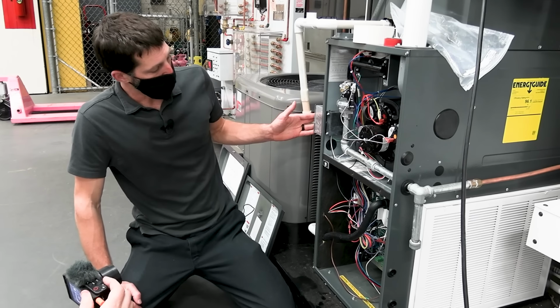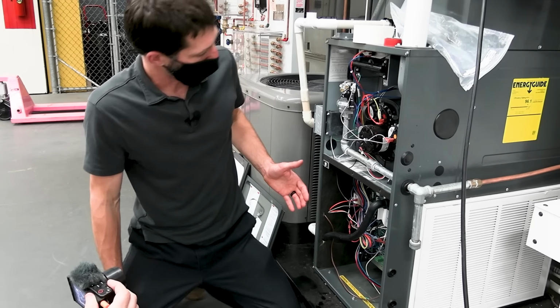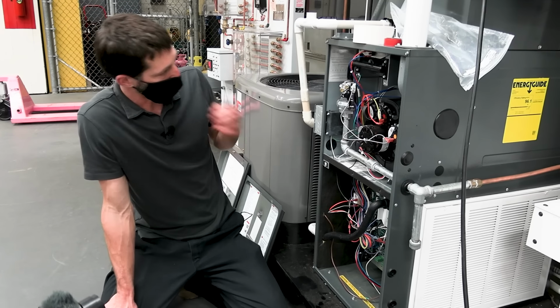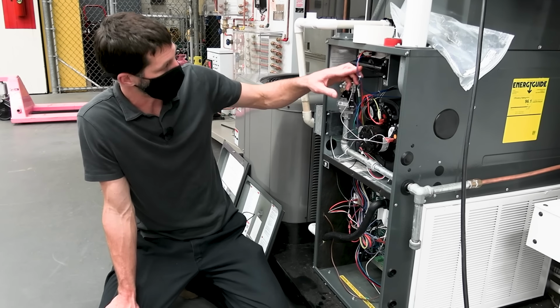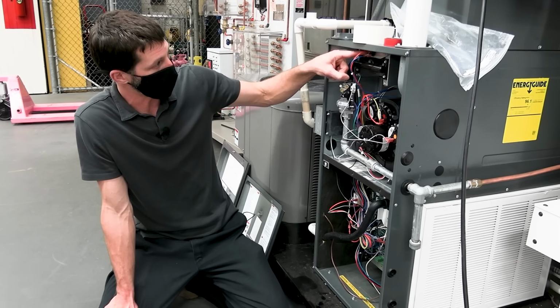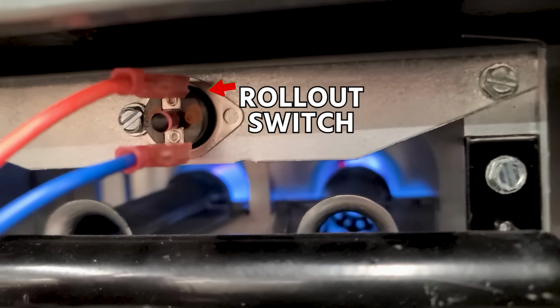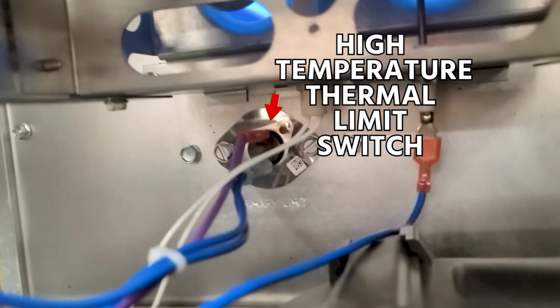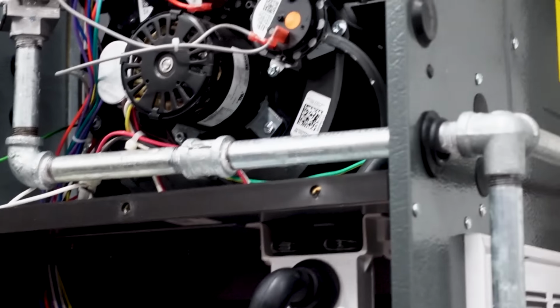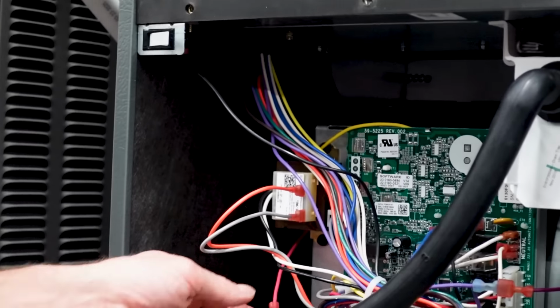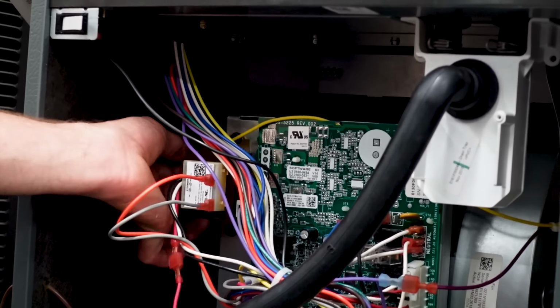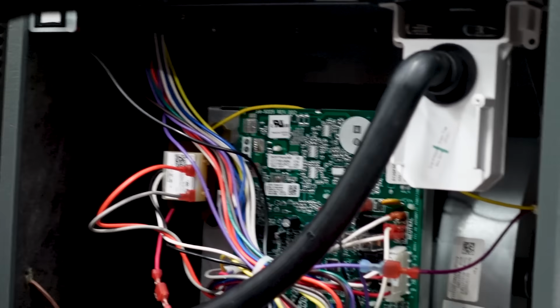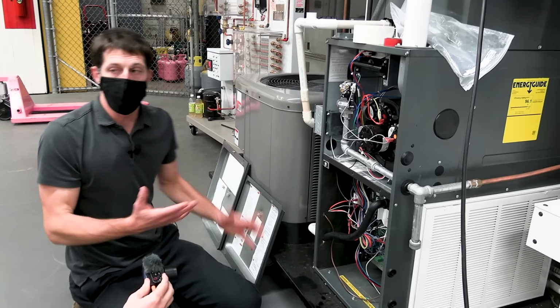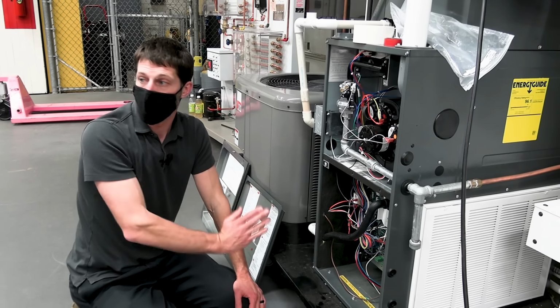When you turn the power on to a furnace such as this right here, it should be sending 24-volt power through all the safety switches, such as the flame rollout switch and the thermal limit. And on this one, there are actually 2 thermal limits on the sides of the blower motor, way back here and way back there. So you see these 2 wires right here, they're leading to a thermal limit switch. There's another one right back here. They're not doing much in a vertical position of a furnace.